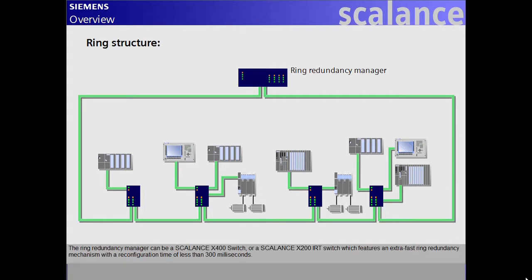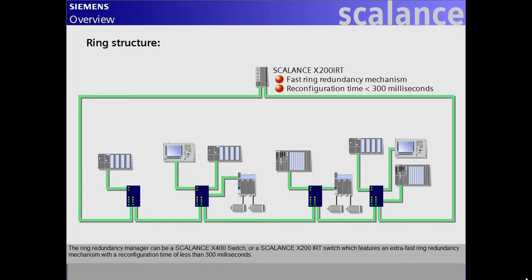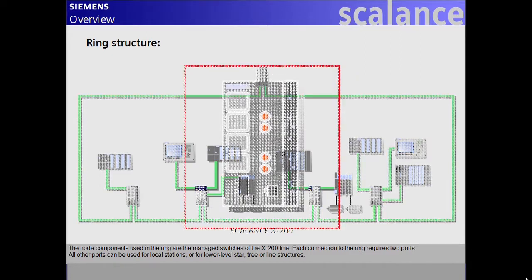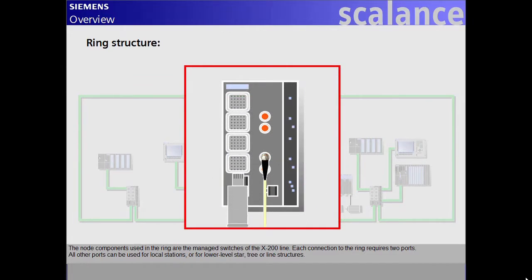The ring redundancy manager can be a Scalance X400 switch or a Scalance X200 IRT switch, which features an extra-fast ring redundancy mechanism with a reconfiguration time of less than 300 milliseconds. The node components used in the ring are the managed switches of the X200 line. Each connection to the ring requires two ports. All other ports can be used for local stations or for lower-level star, tree or line structures.